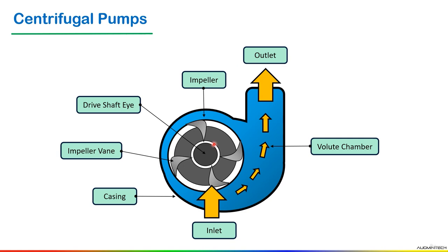Remember, centrifugal type fire water pumps generate centrifugal force by rotating their impellers and throwing the water from the center of the impeller to the outer part of the impeller. Centrifugal fire pumps are used for high flow rate to provide a constant water flow, mainly for buildings, utility stations, etc. A fire pump in a fire sprinkler system normally receives water from either an underground water supply or a water tank, lake or reservoir. These pumps are powered by electricity or diesel fuel.